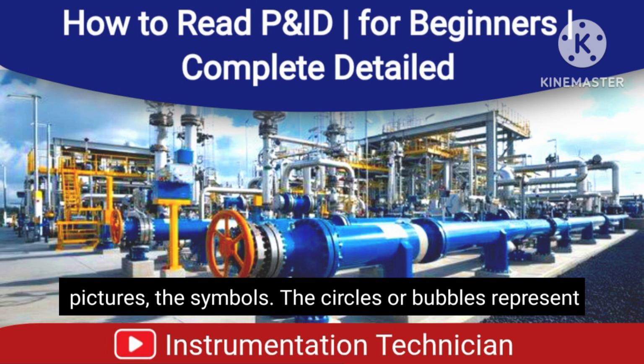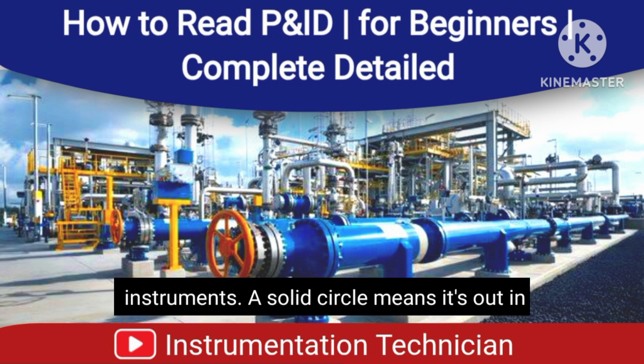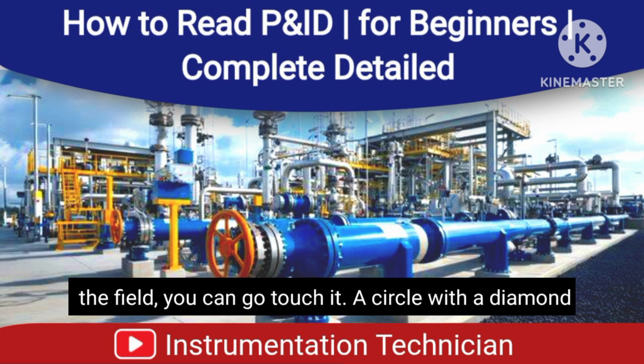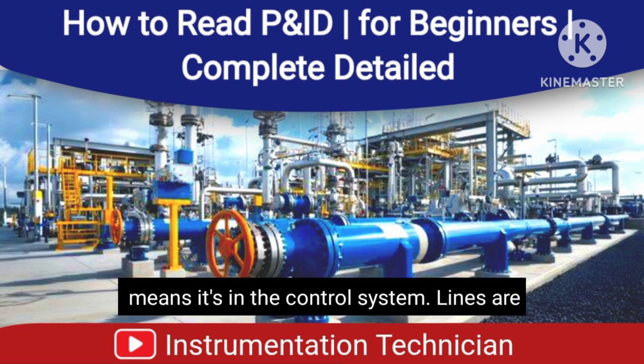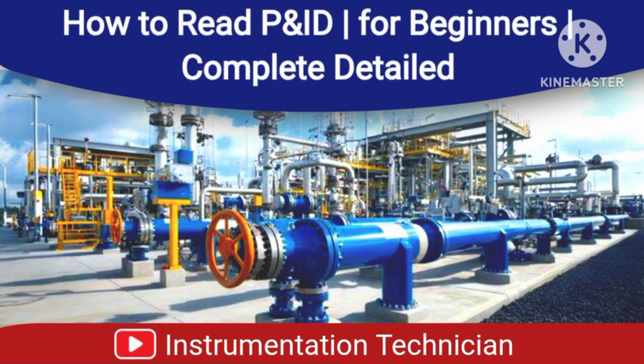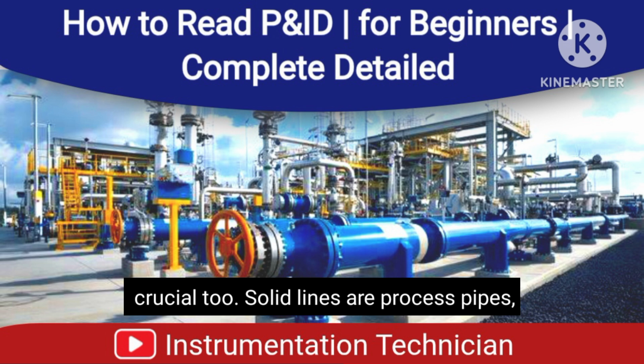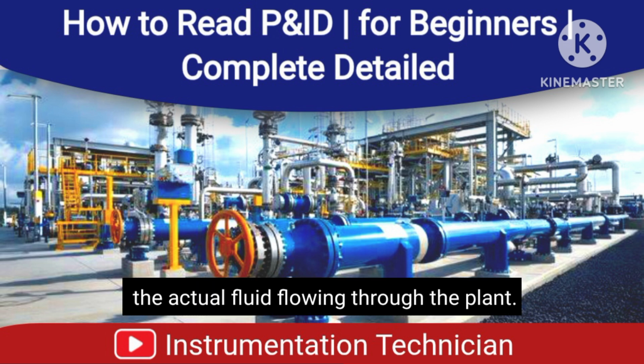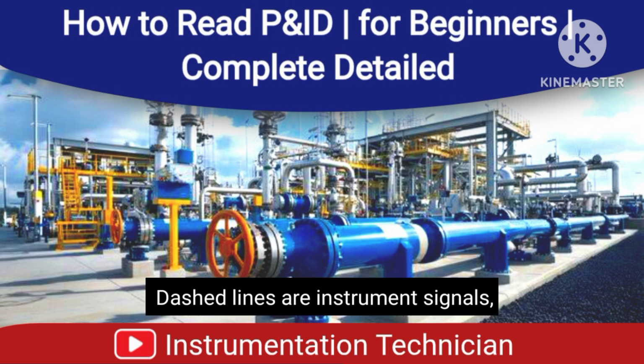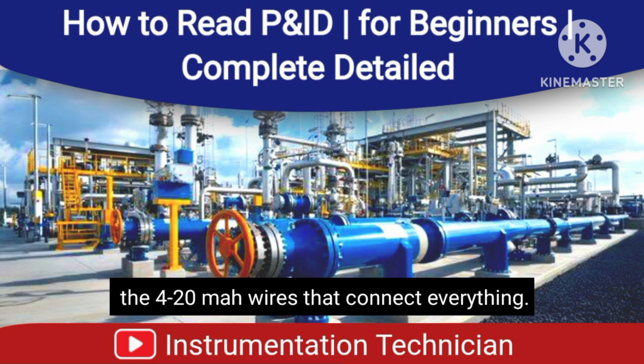Now let's talk about the pictures, the symbols. The circles or bubbles represent instruments. A solid circle means it's out in the field, you can go touch it. A circle with a diamond means it's in the control system. Lines are crucial too. Solid lines are process pipes, the actual fluid flowing through the plant. Dashed lines are instrument signals, the 4 to 20 mA wires that connect everything.